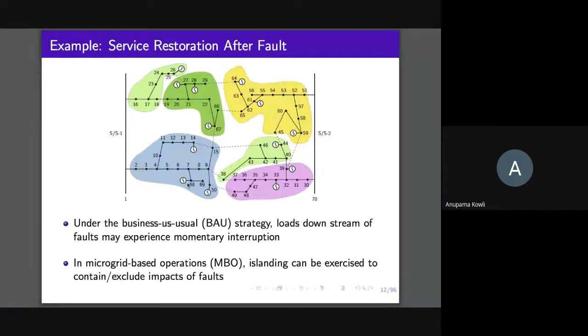And what we want to do is then exercise the islanding option that a microgrid naturally provides, either to contain the impact of a fault within that microgrid itself, or to exclude the impact of a fault occurring outside the microgrid. In doing so, you make sure service interruption is minimized as much as possible. So for example, if the fault was to occur in 5-6, we want to break this up into a microgrid and another microgrid, making sure the impact of the fault is contained outside the microgrid and doesn't percolate within it, so fewer loads experience a service interruption. Is the concept sort of clear at a higher level?